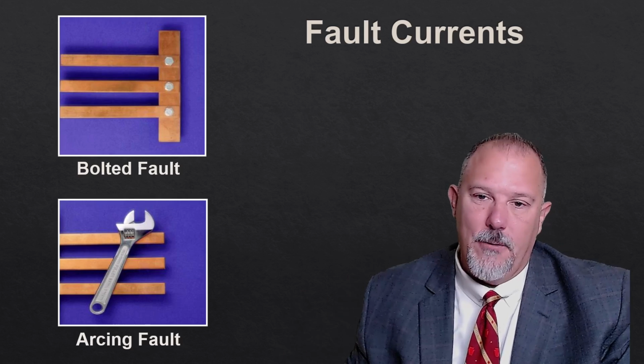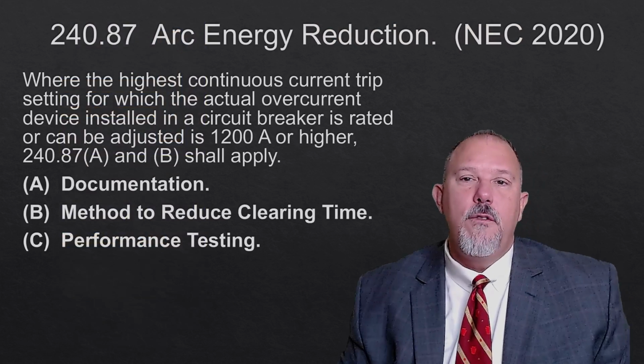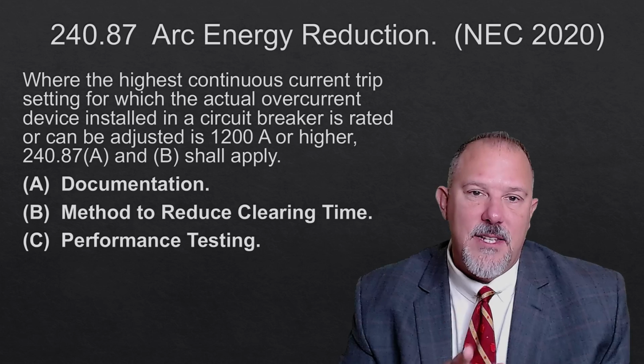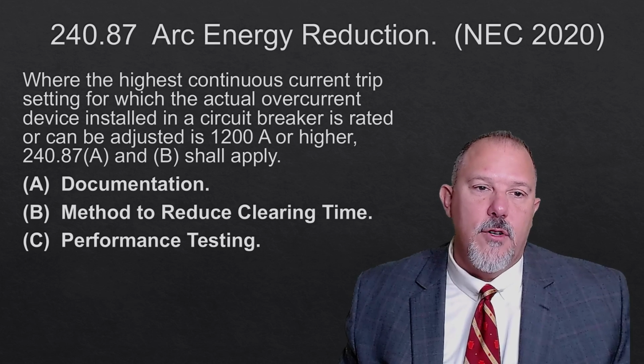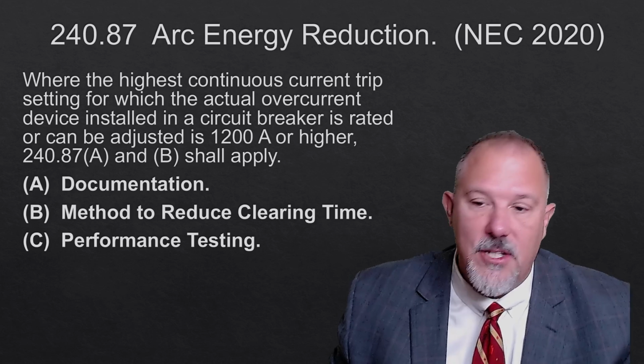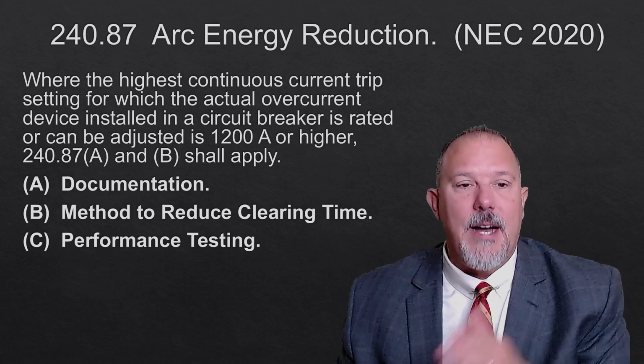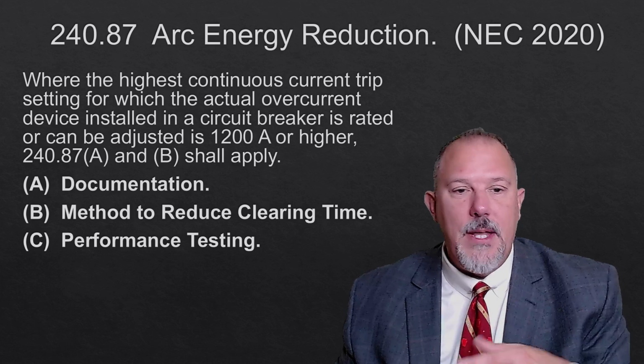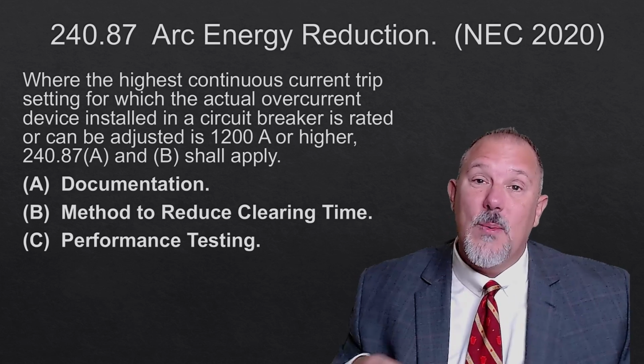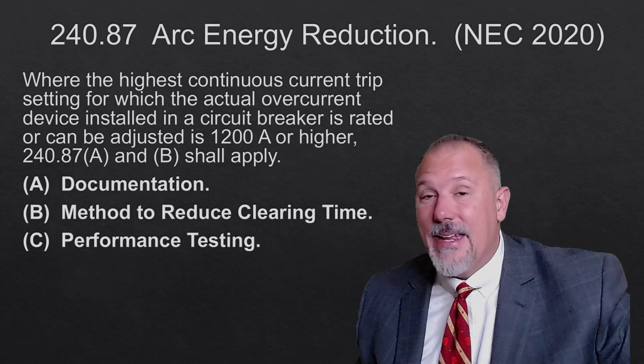Now, 240.87 language says where the highest continuous current trip setting for which the actual overcurrent device installed in a circuit breaker is rated or can be adjusted is 1200 amps or higher. You have A and B, and technically in the 2023 code, we're going to fix this. It's A, B, and C apply.